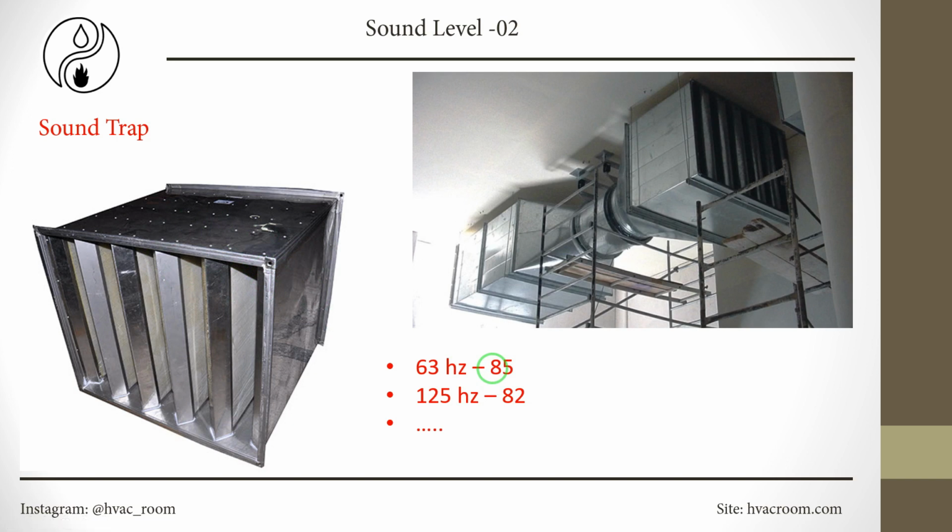But please remember, the lower the dB goes, the higher the pressure drop of this unit goes. So that's another thing that you might consider: how much pressure drop you are going to add to the external static pressure of the system.